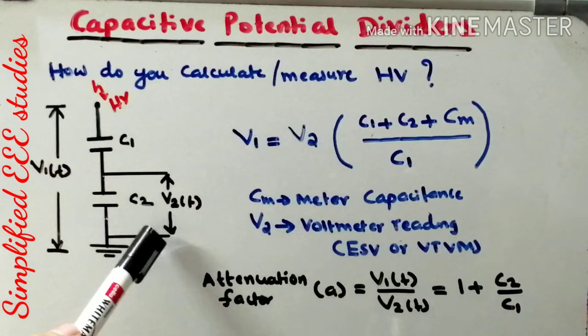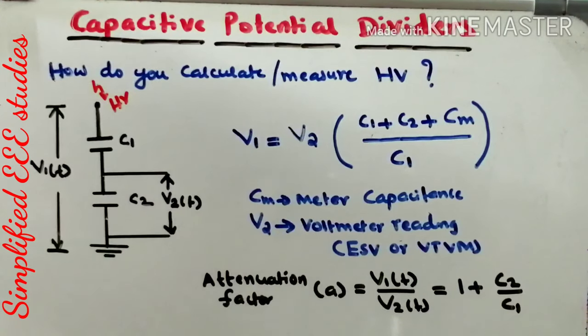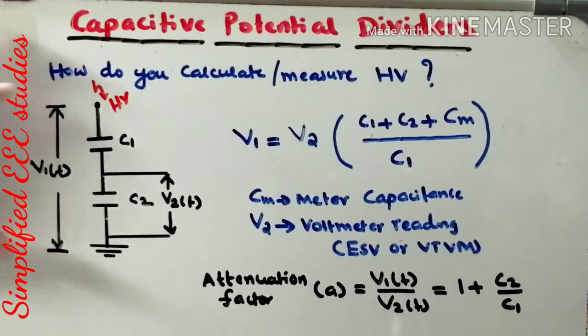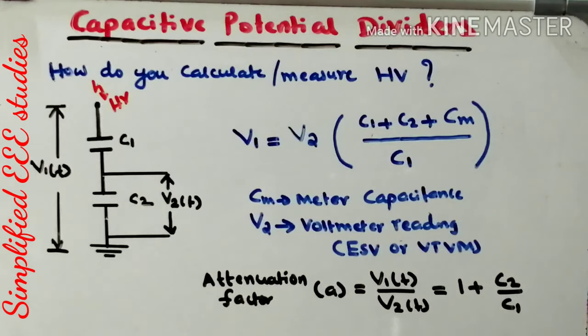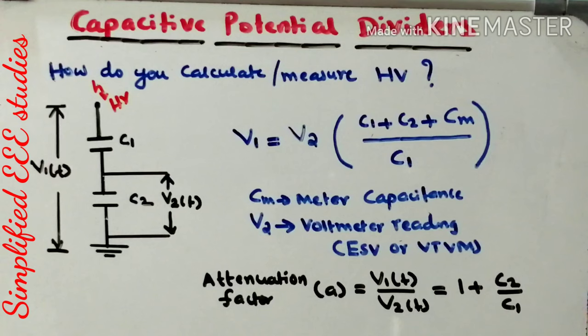Let us consider the schematic diagram of Capacitive Potential Divider. The whole high voltage is divided with the help of Capacitors C1 and C2. This is the low voltage arm — V2. This particular term is the low voltage arm, and this will be the high voltage arm. We have to measure V2 with the help of either an Electrostatic Voltmeter or VTVM. You should know the value of Capacitors C1 and C2. C1 is the high voltage capacitor and C2 is the LV capacitor, made up of either mica or paper. Moreover, you need to know the meter capacitance, which will be in the range of 10 to 50 pF.